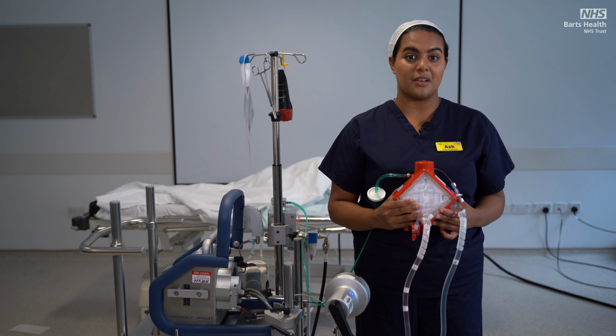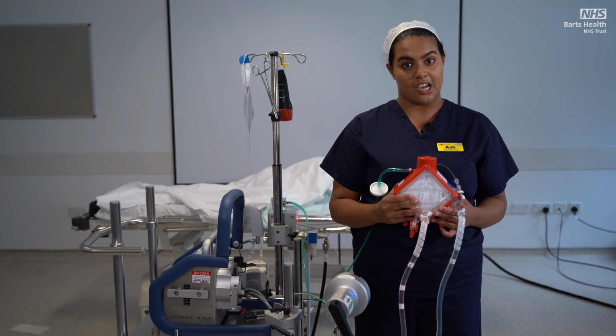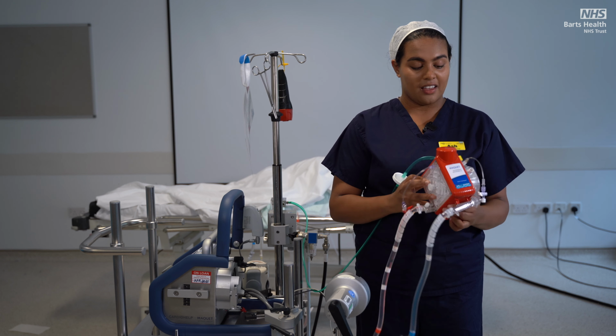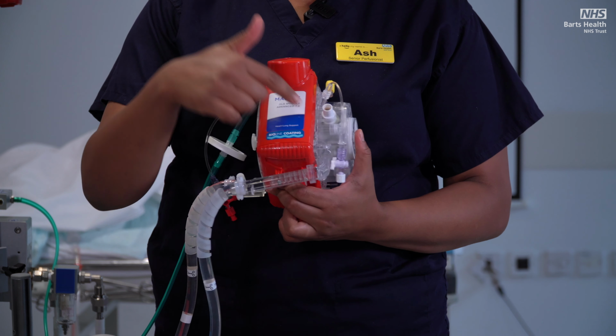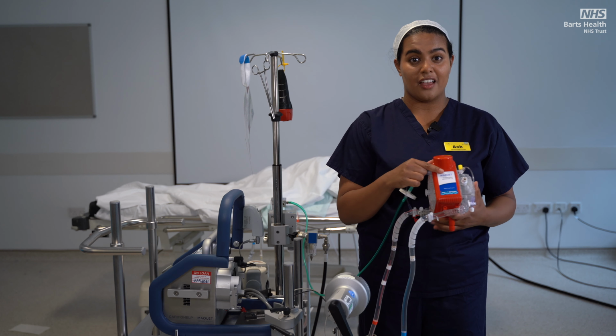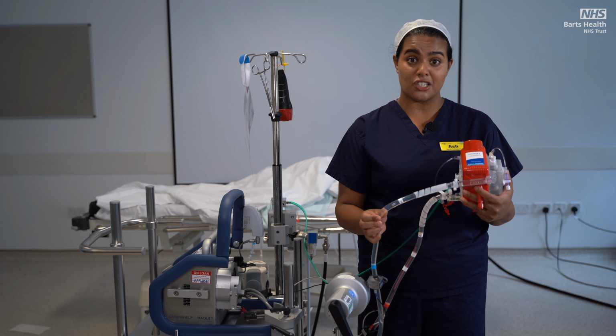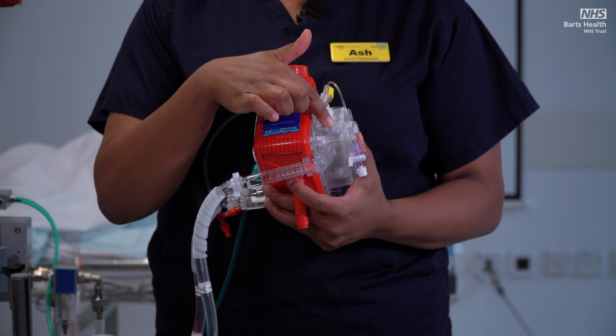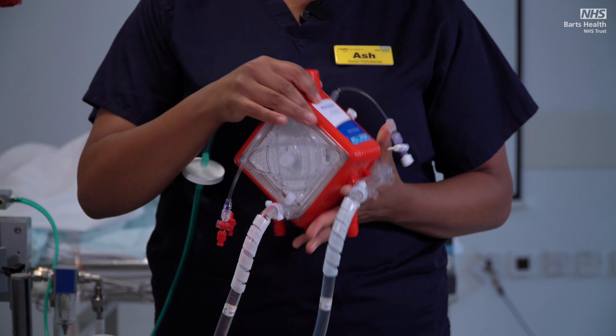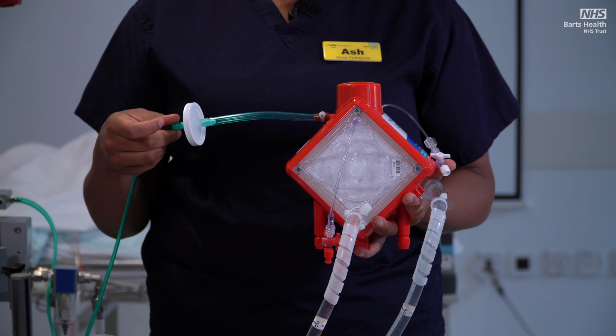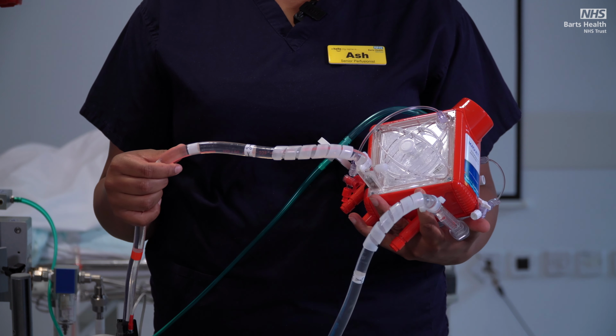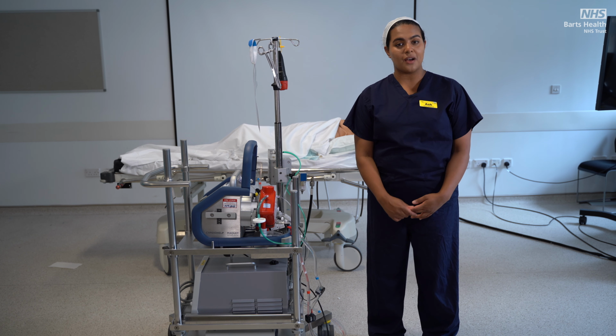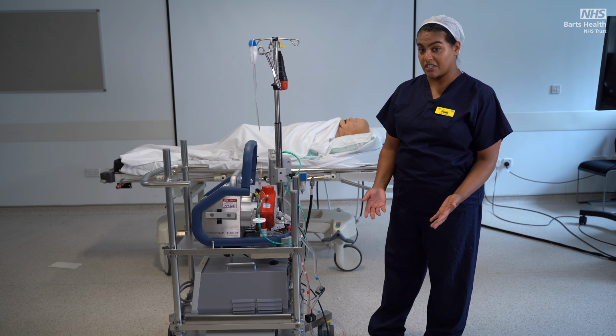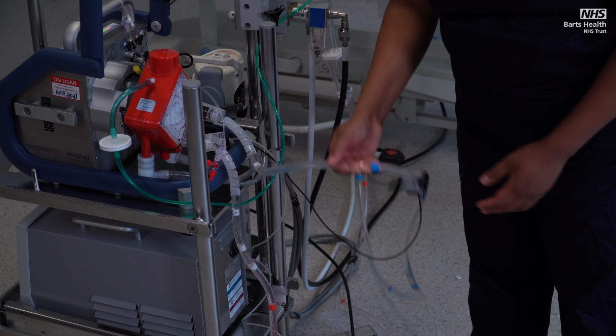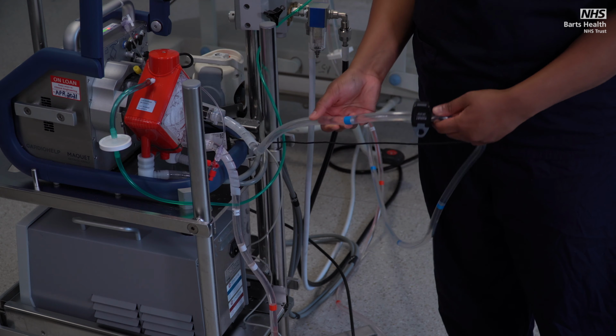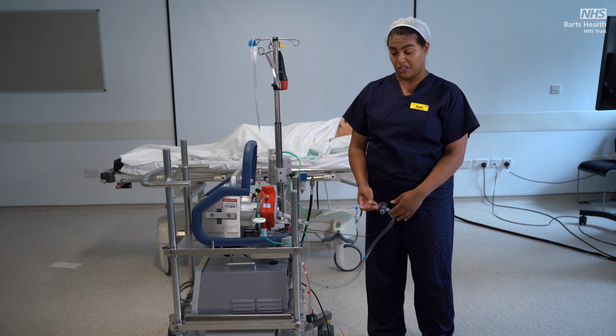The Cardiohelp ECMO circuit is centered by the red diamond oxygenator. This is the centrifugal pump, which is backed onto the oxygenator. The blood travels down the drainage line into the centrifugal pump, pumped into the oxygenator, where gas is added via the green line before going into the return tubing and back to patient. As the blood passes down the drainage tubing under negative pressure, the first place it's going to meet is your venous bubble sensor, where any bubbles from this side will be detected in the intervention menu.